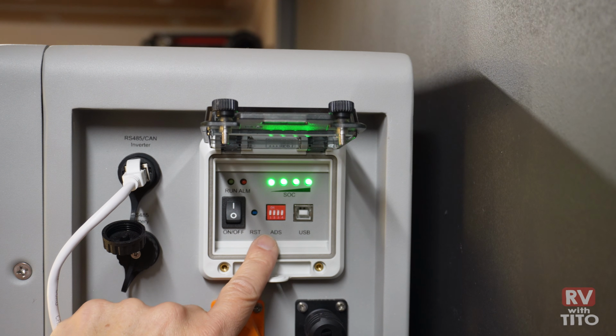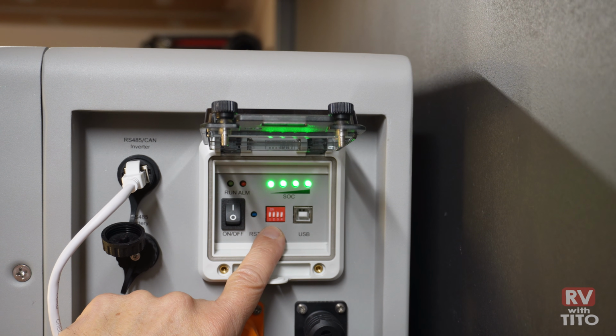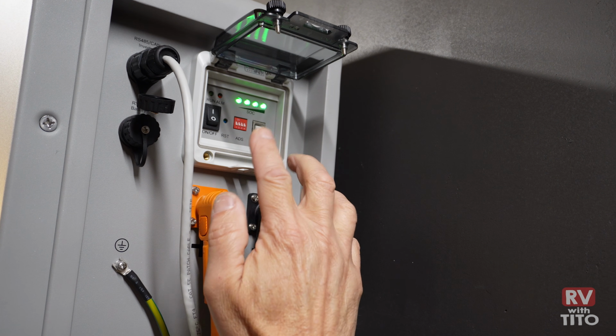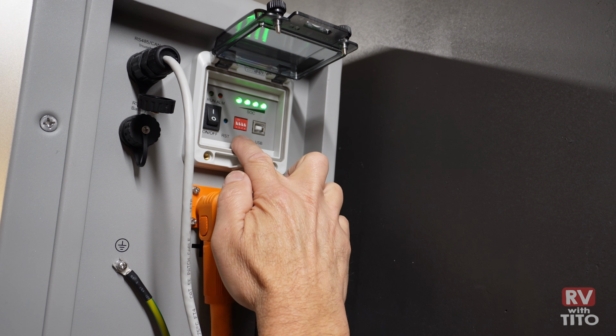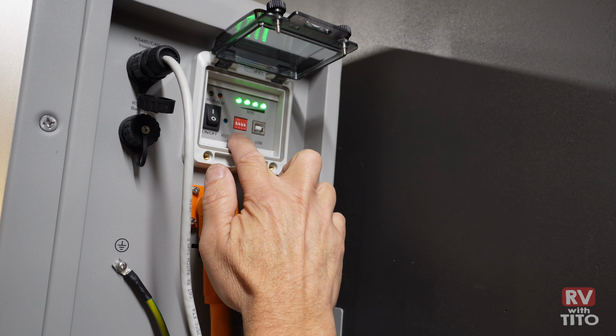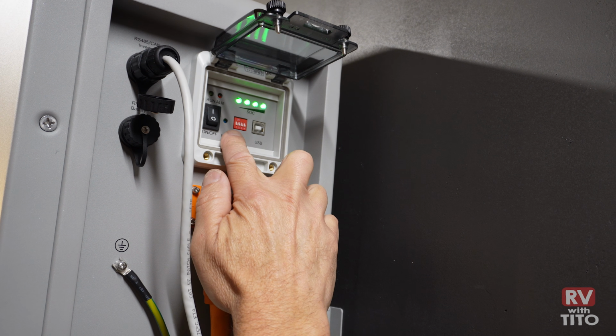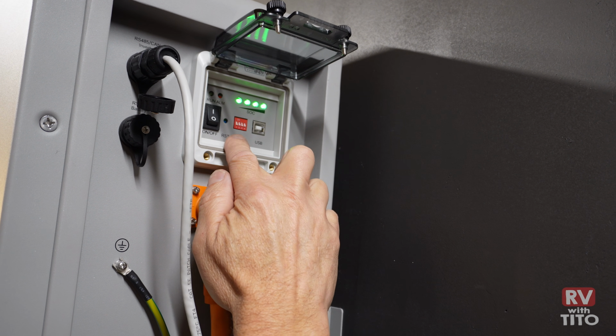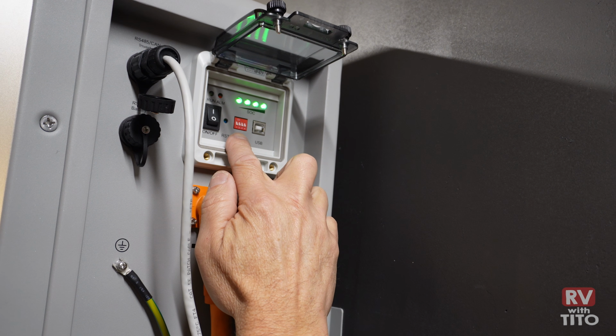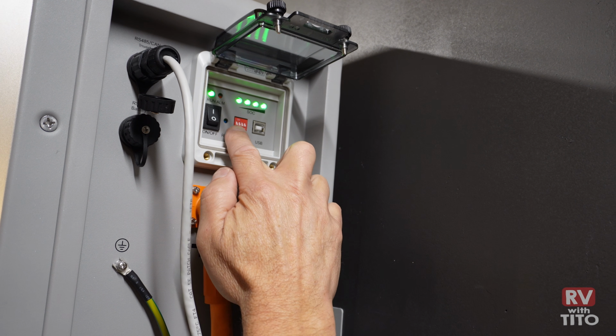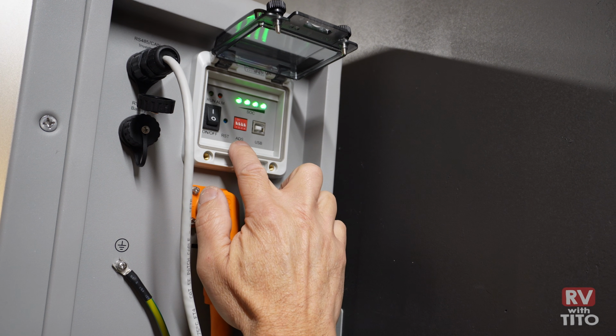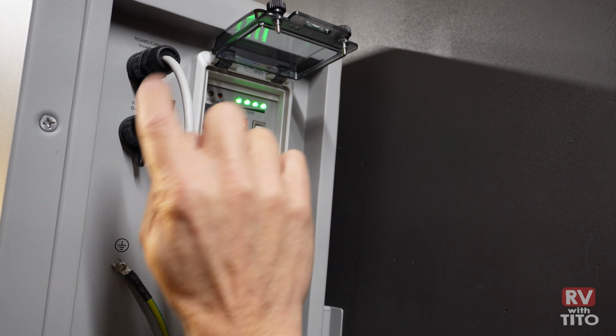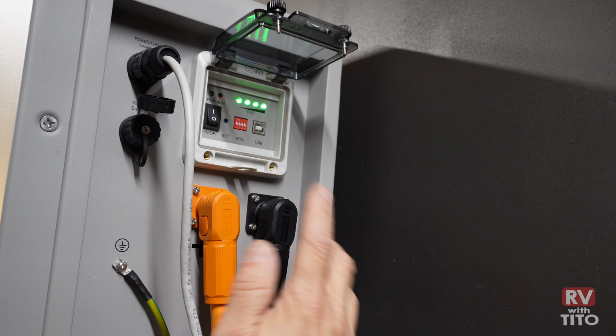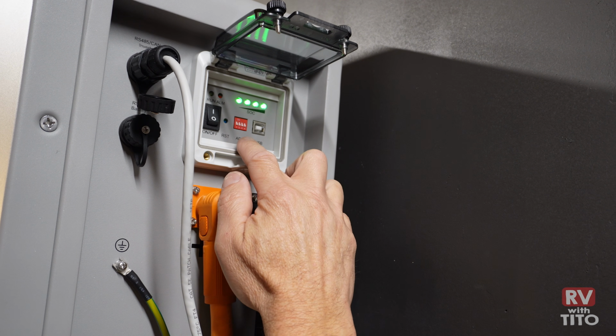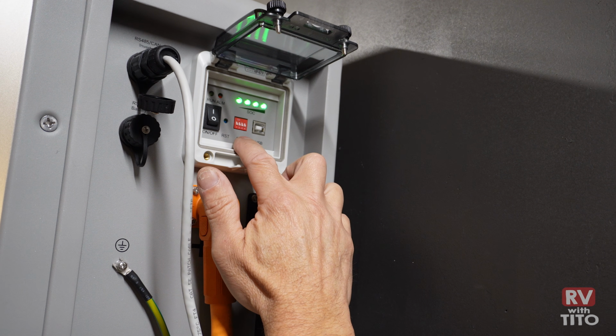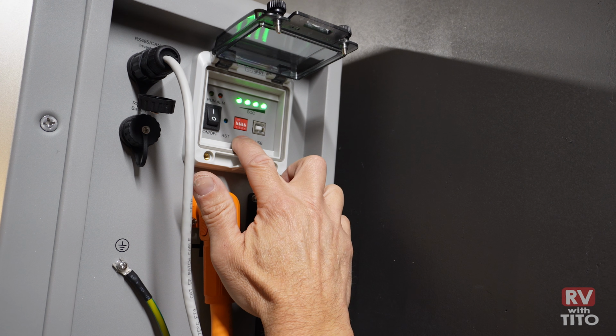Now in the middle here we have our dip switches, and this is going to identify all our batteries if we have multiple. For standalone operation, we just want everything in the down position for one battery, but if you have one or more, you can do up to 16, then you'd set these accordingly. This would be number 1 as a master, then set to number 2, 3, all the way down the chain, so the BMSs get identified appropriately.